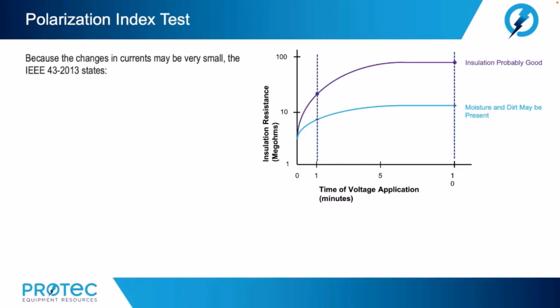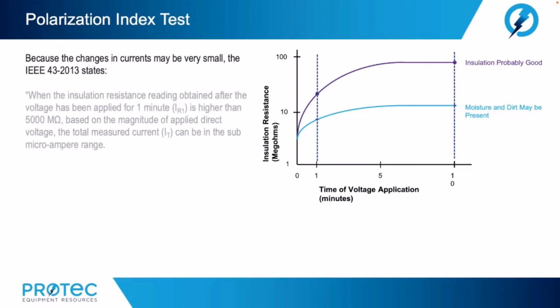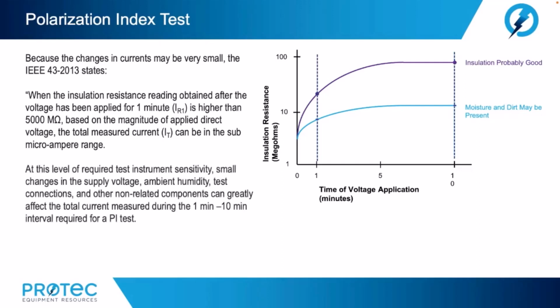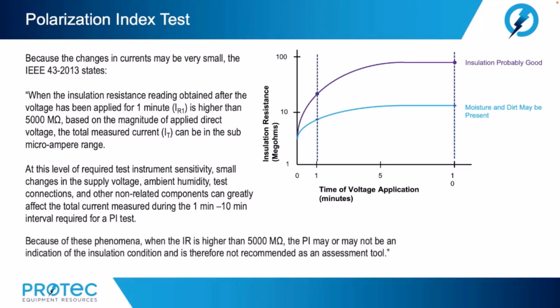Because the changes in current may be very small, the IEEE 43-2013 states, when the insulation resistance reading obtained after the voltage has been applied for 1 minute is higher than 5,000 megohms based on the magnitude of applied direct voltage, the total measured current can be in the sub-microamp range. At this level of required test instrument sensitivity, small changes in the supply voltage, ambient humidity, test connections, and other non-related components can greatly affect the total current measured during the 1 minute to 10 minute interval required for a PI test. Because of these phenomena, when the insulation resistance is higher than 5,000 megohms, the polarization index may or may not be an indication of the insulation condition and is therefore not recommended as an assessment tool.